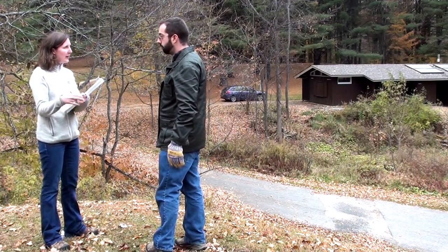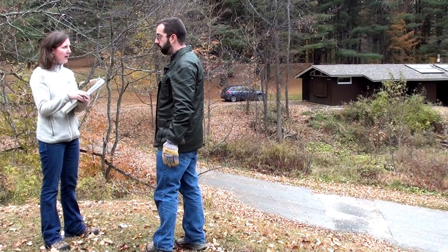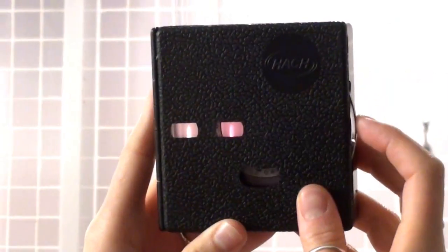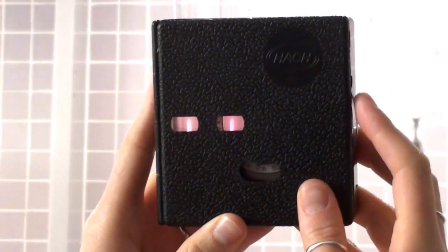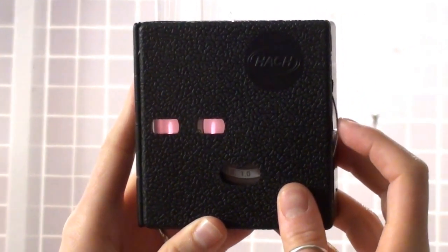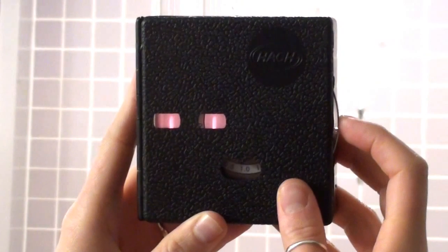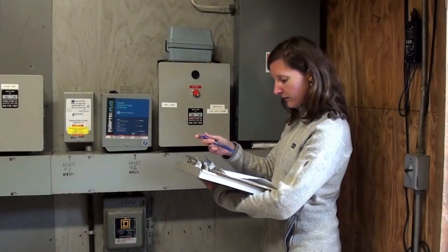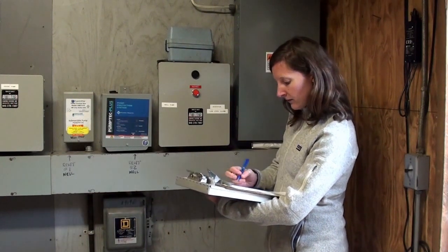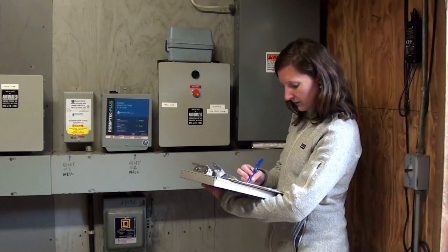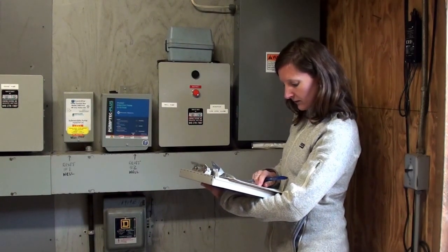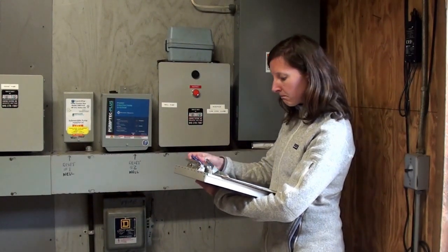If your system uses a chemical disinfectant, it's a good idea to take a chlorine residual during the assessment. The residual should be close to where you would expect it. A chlorine residual lower than expected could be a sign of contamination or of a sanitary defect. This is also a good time to review monthly reports and other records to identify recent water production data and chlorine residuals to see if they can point to any potential issues in the system.